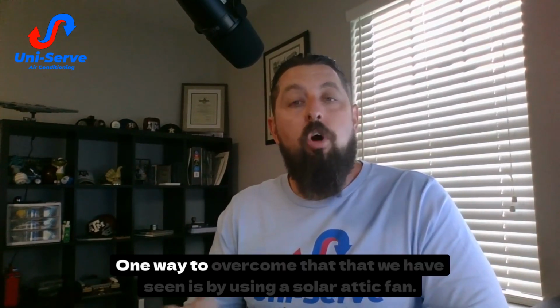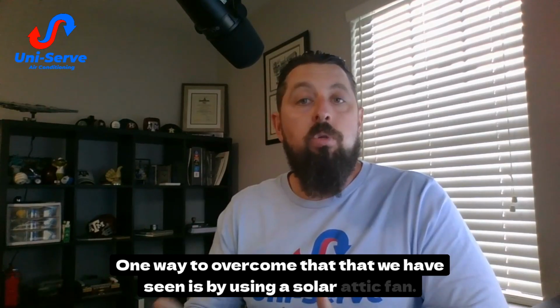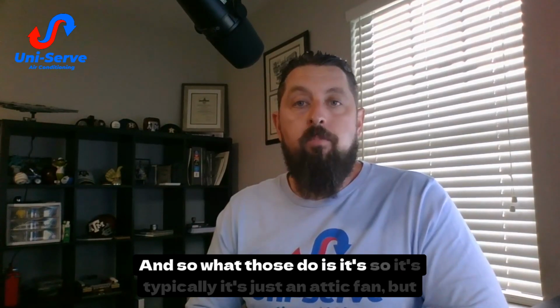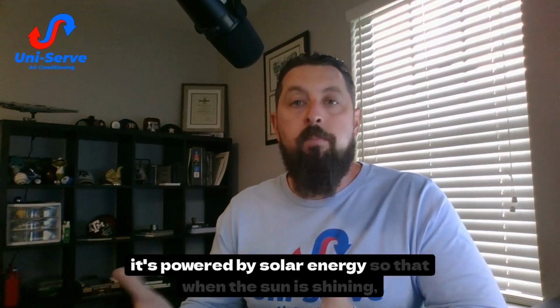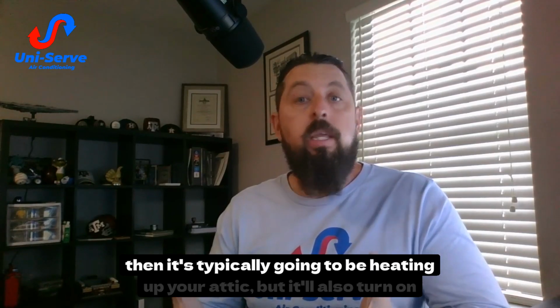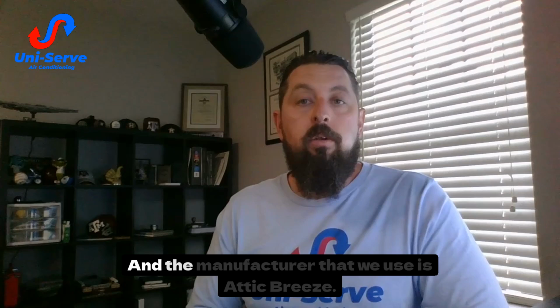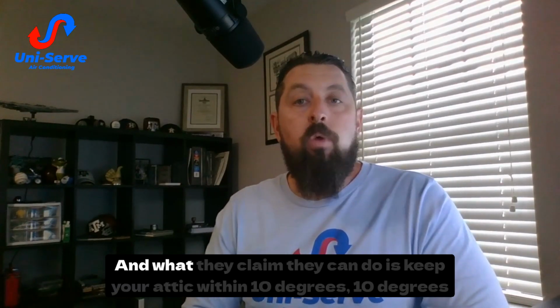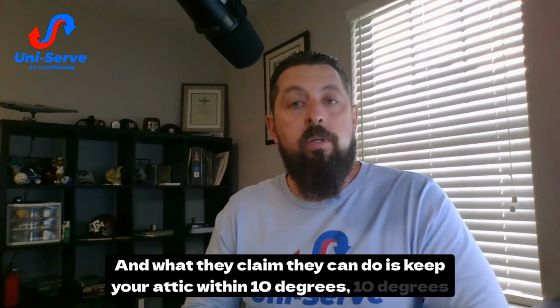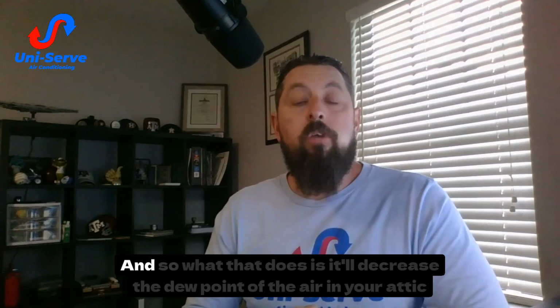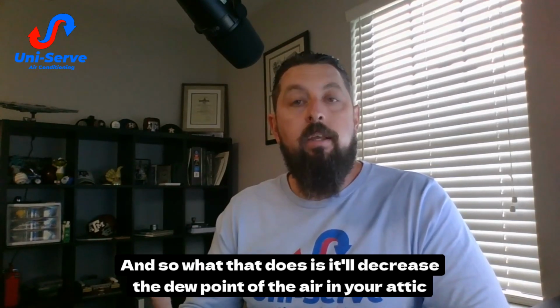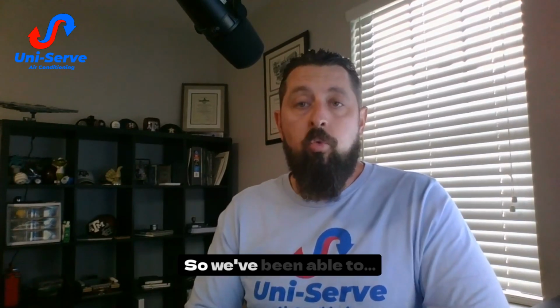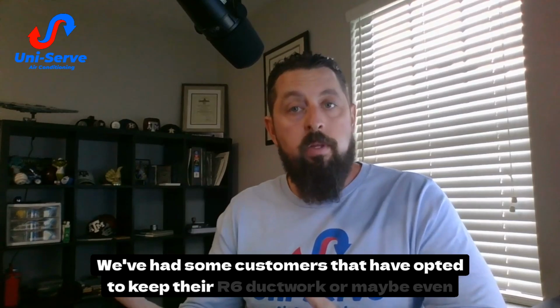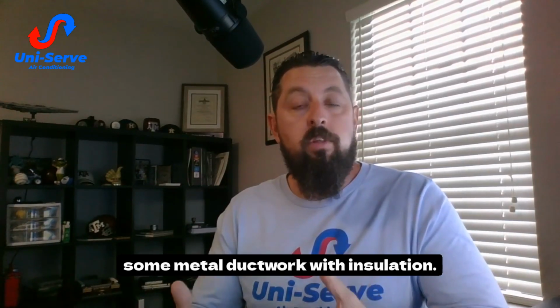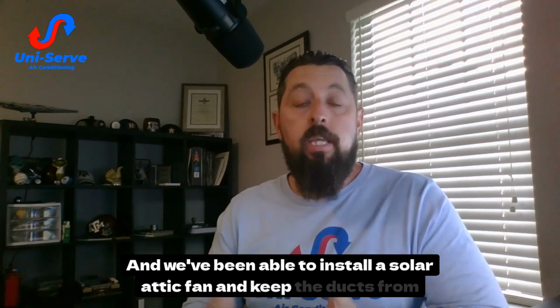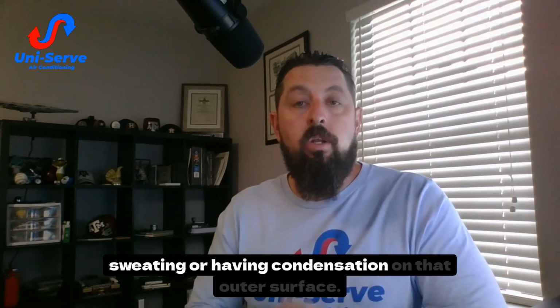Just a quick tip here. One way to overcome that, which we have seen, is by using a solar attic fan. It's just an attic fan, but it's powered by solar energy, so when the sun is shining and heating up your attic, it'll also turn on that attic fan. The manufacturer that we use is Attic Breeze, and what they claim they can do is keep your attic within 10 degrees or less of the outside air temperature. That will decrease the dew point of the air in your attic and can prevent condensation on ductwork. We've had some customers opt to keep their R6 ductwork, or even some metal ductwork with insulation, and we've been able to install a solar attic fan and keep the ducts from sweating or having condensation on that outer surface.